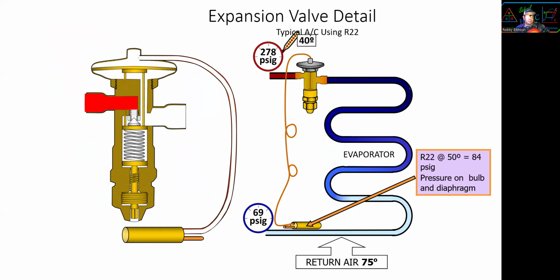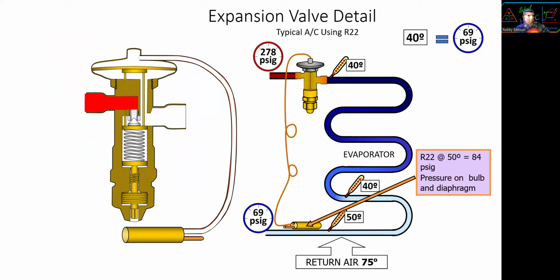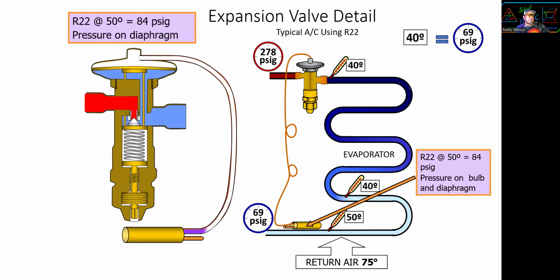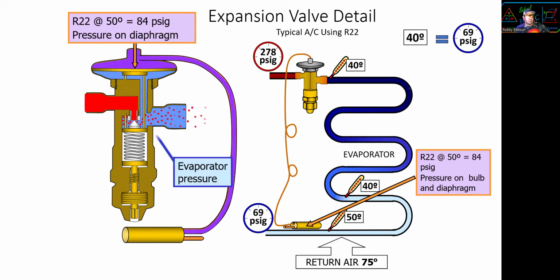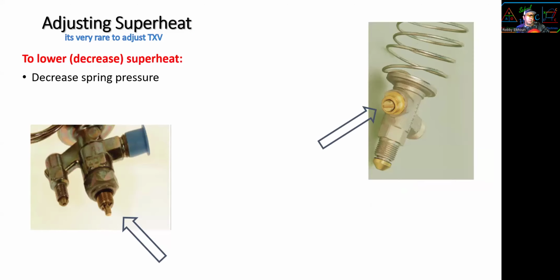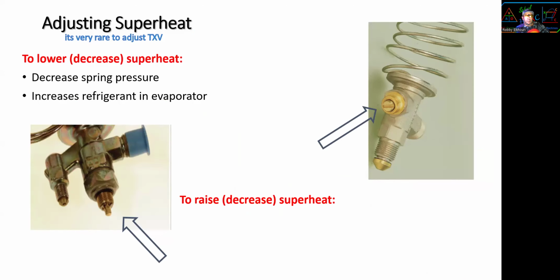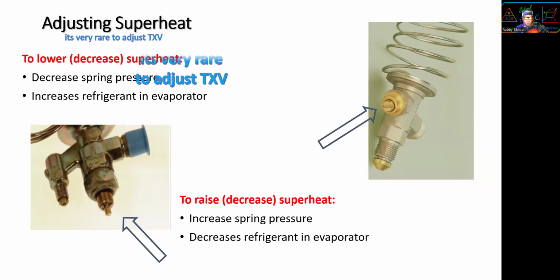Next, expansion valve details. Temperature 40, 40, and 50 superheat. Between 40 and 40 is your saturation liquid-vapor mix, latent heat, and 40 to 50 is your sensible heat, or superheat. So now the valve will adjust. The temperature at the end of the evaporator is 50 degrees. 50 degrees equals 84 pressure on the diaphragm. The diaphragm will push, adjusting against evaporator pressure and spring pressure. To lower superheat, decrease spring pressure, which increases flow. To raise superheat, increase spring pressure, which decreases refrigerant in the evaporator.